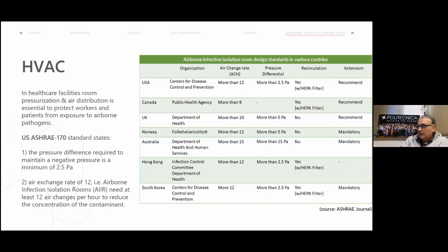Then at the end of the story, if you are really in great difficulty because of the tightness of the room, if the room is not sealed correctly, if it has a lot of cracks or infiltration and you cannot solve it, of course it's impossible to have a good under pressure inside. But at least you must have a flow rate. Of course, this is not an acceptable situation, but sometimes it is impossible to do something else. So in this case, the important thing is that when you open the door just a little, the air moves from outside to inside along all the gap of the door. The last one is a very critical situation, but it's better than nothing. So this is more or less what you can do.